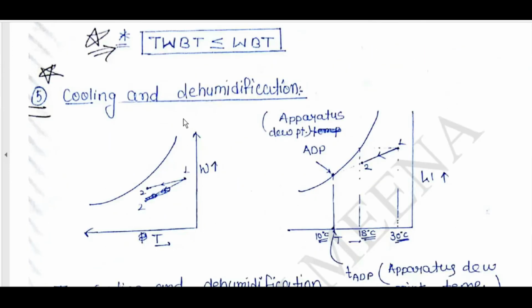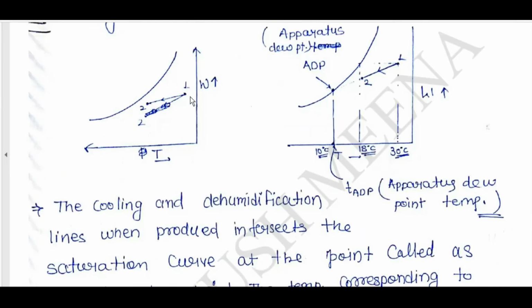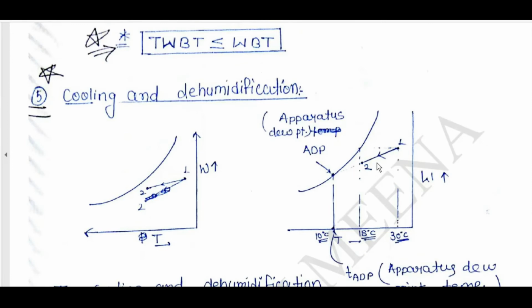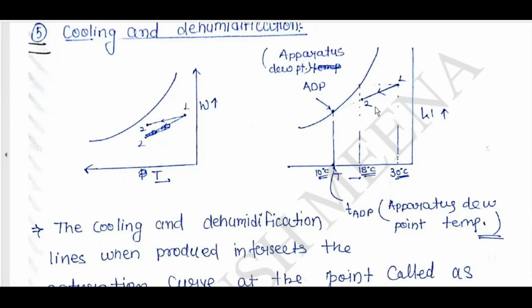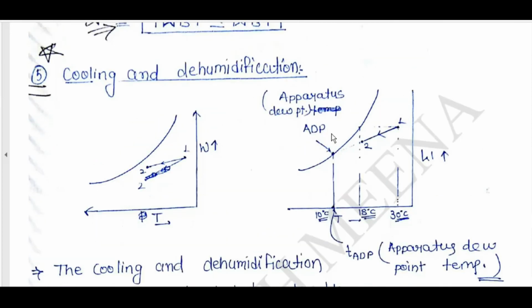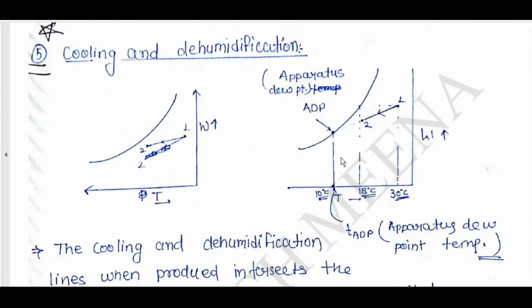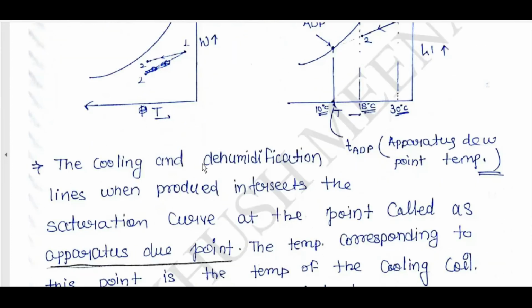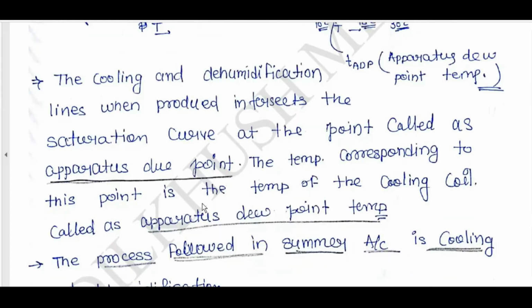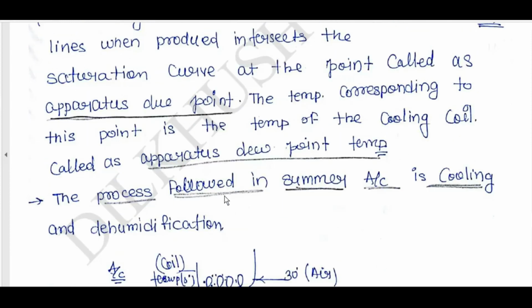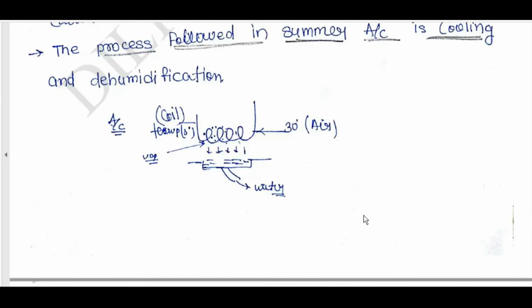Cooling and dehumidification: temperature decreases and W also decreases. The point at which the process line, when produced, intersects the saturation curve is the apparatus dew point. The temperature corresponding to this point is the temperature of the cooling coil, called the apparatus dew point temperature. The process followed in summer air conditioning is cooling and dehumidification.